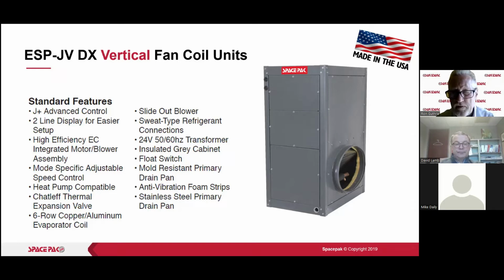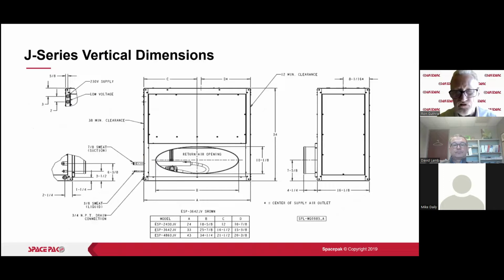All right, we only have a 1/4 inch of static pressure to work with on the return side. Right, and if you look on the back of your duct calculator, you'll see differences in equivalent feet of duct on the different fittings, and just a box underneath there is a pretty high pressure drop, so it's a pretty high equivalent length of duct. So you should really have a 90 that turns and has turning vanes in it if you're going to do that, but it's possible. All right, as you'll see over to the right there on the bottom, 16 1/8 inch. We don't have that same 14 1/8 on this unit, so it's not going to fit between two joists anywhere. But it's made to go into a closet or in the basement and flow air upward.